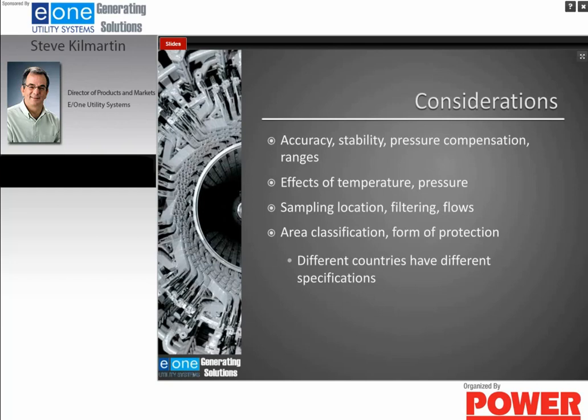Again, area classification: you're bringing hydrogen into this sensor. When you bring hydrogen to this sensor, the area becomes a hazardous area. Again, different countries have different requirements. In the United States, the National Electrical Code, for Class 1, Div 2, Group B requirements.